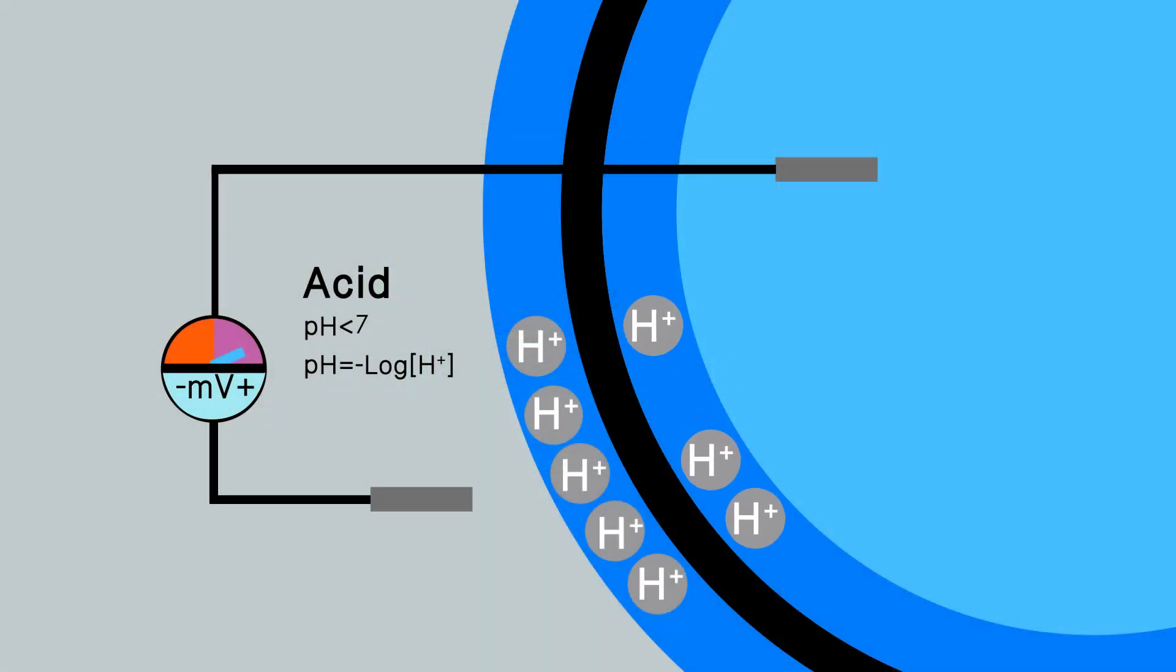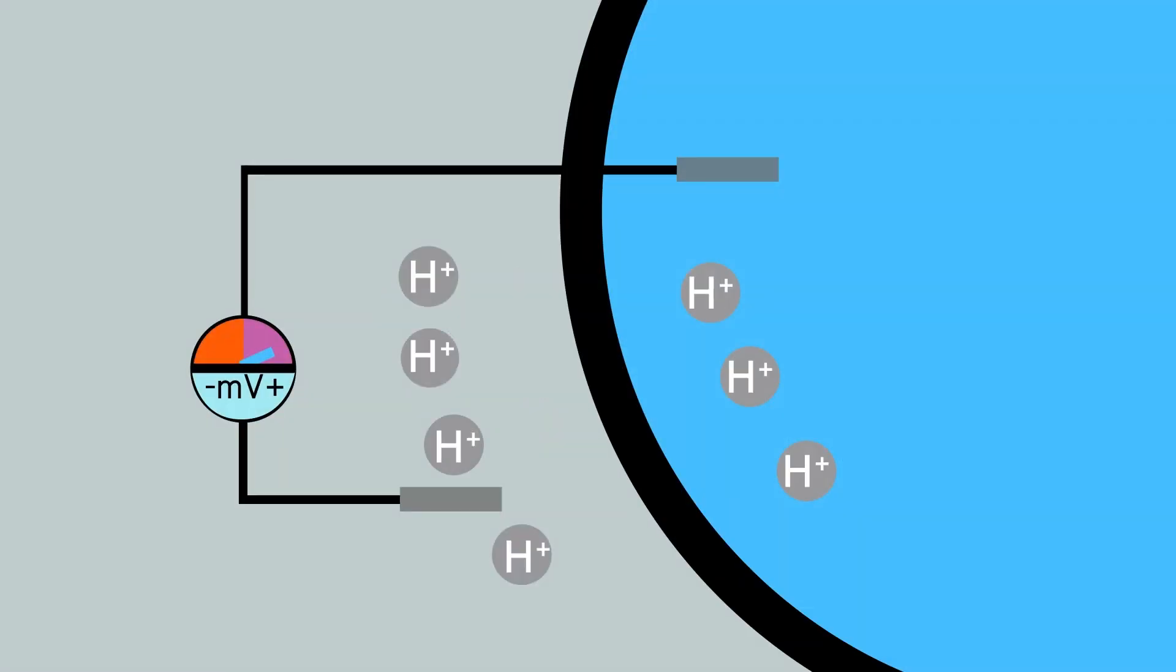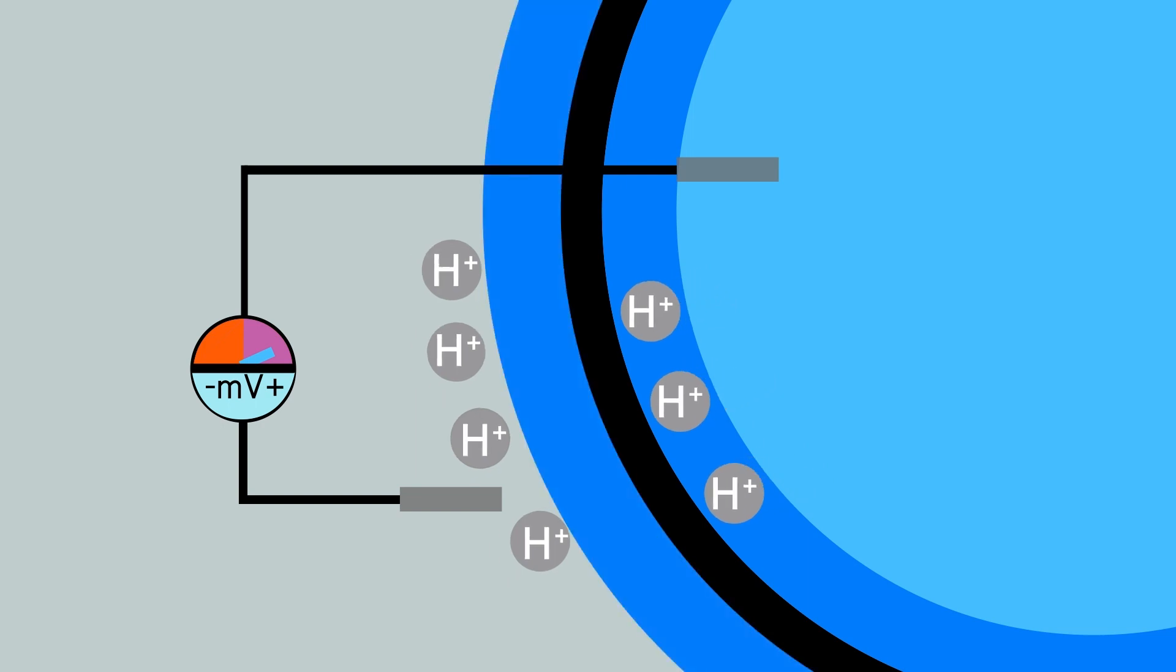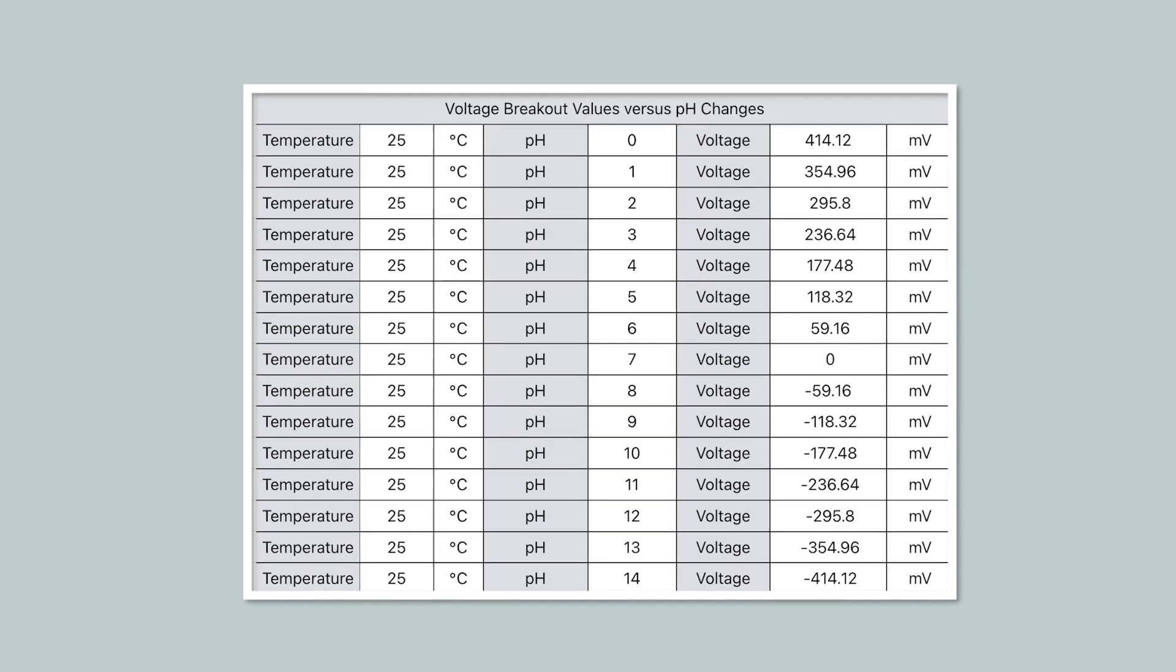The last video explained how a pH meter converts the concentration of hydrogen ions to the voltage signal and outputs it to devices like main controllers through amplifier. The sensed concentration change is the potential change on the outer glass electrode. There is a linear relationship between millivolt signals and pH values.